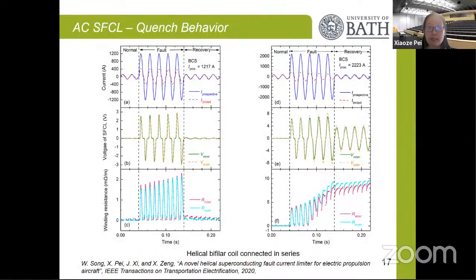So this is some of the experimental result on the helical bifilar coil. When the prospective fault current is 1,200 amps, you can see the blue curve is the prospective fault current. Without a fault current limiter, it will go up to 1,200. And with the fault current limiter we designed, the current is limited to the red line, which is just below 400 amps. So you can see this is a significant reduction of the fault current in the system. And we observed the resistance across the coil.